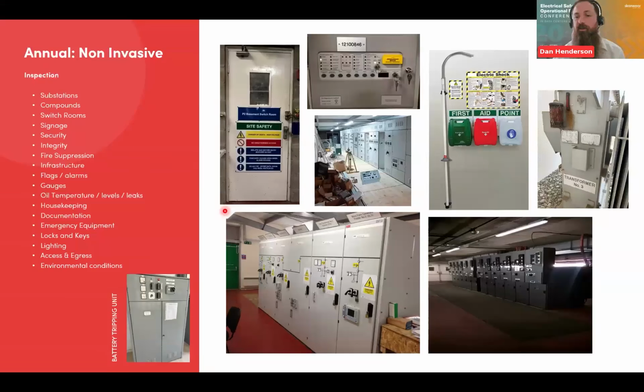Emergency equipment, so things like your rescue hooks, your signage, any first aid equipment such as eye wash bottles, fire extinguishers, anything that's provided for emergency circumstances. Locks and keys, so things like keys for your panels, your operational locks, keys for your battery tripping units. Without those, you're not going to get access. You're not going to be able to do an inspection. And you'd be surprised the amount of those that go missing and you can't get access to them.